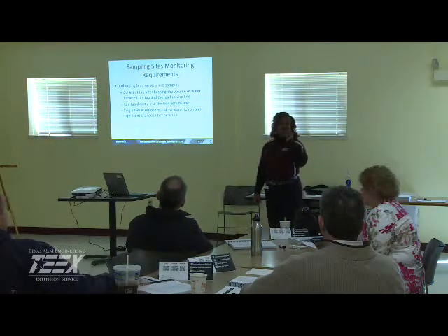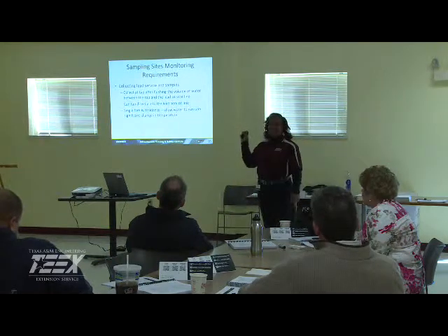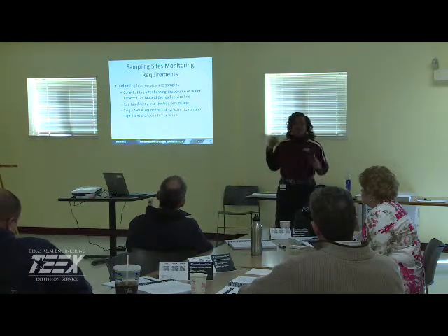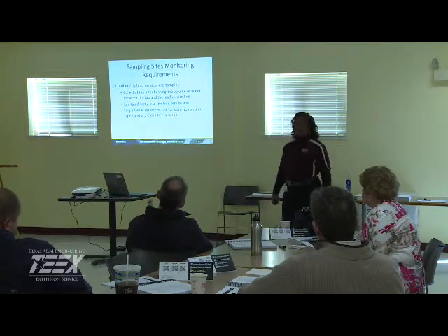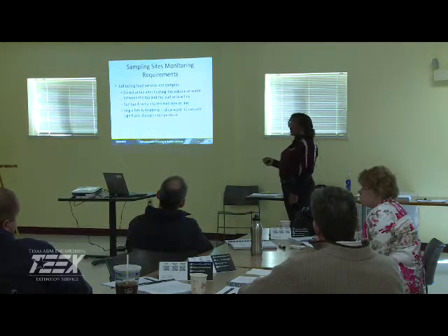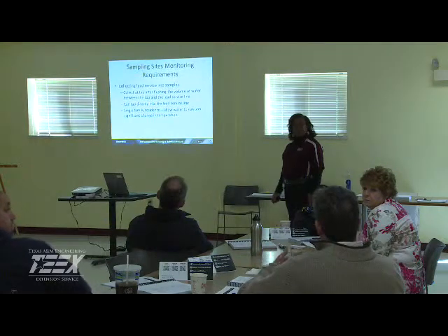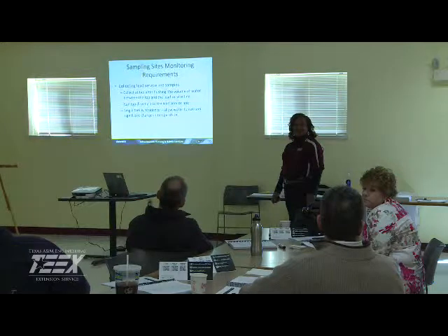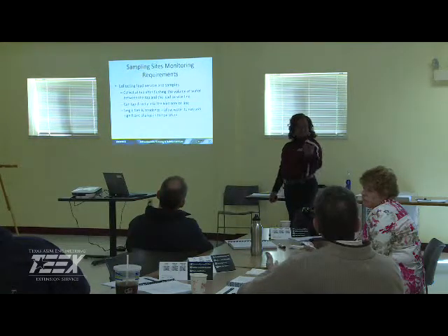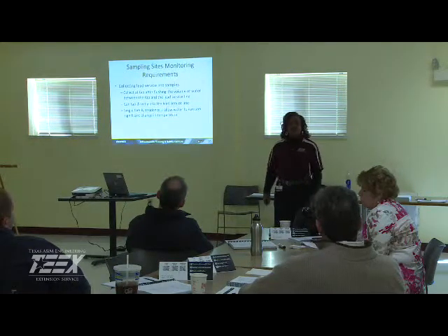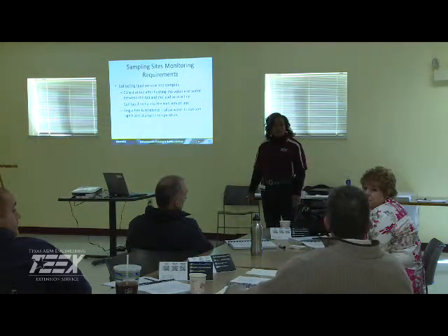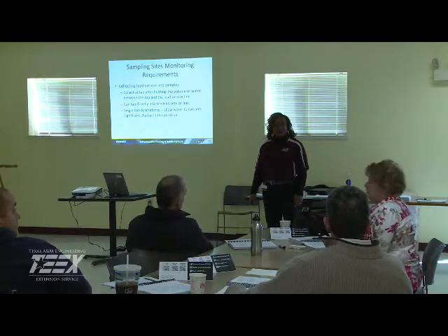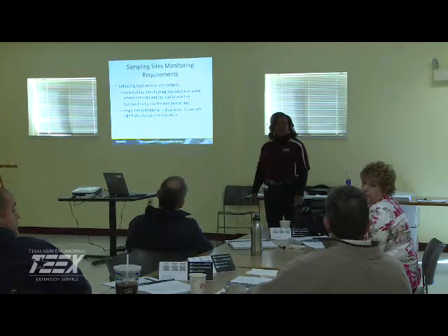Okay, excellent. That's another thing that's stipulated and specified, that you give those results back to the consumer. Sampling first thing in the morning helps, because usually everyone's getting up and the water hasn't been used. We usually suggest that when you come home from work, if no one's been home, there's your 6 to 8 hours. Excellent. And you usually do more than the minimum number. Yes, as I recall. You always want a few extra samples.